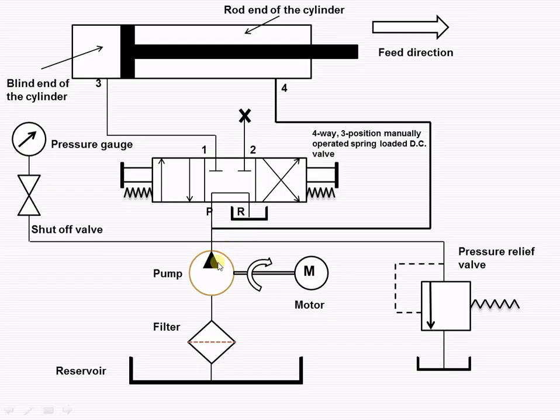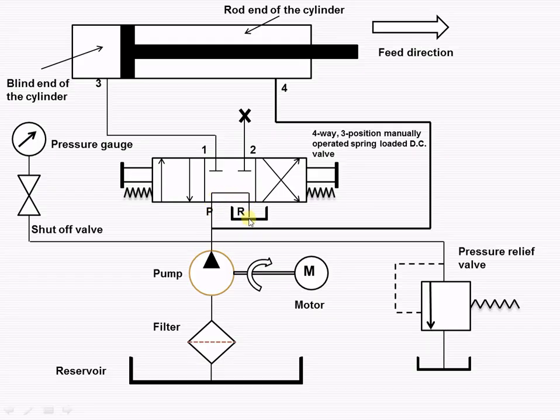In the given neutral or block position, from the reservoir, when the motor drives the pump, the fluid enters into the filter, gets filtered, is pumped by the pump, and goes to port P and then back to the reservoir. This is the neutral or block position — nothing will happen in this particular case.